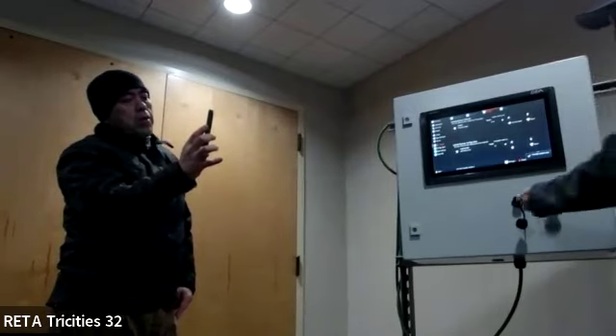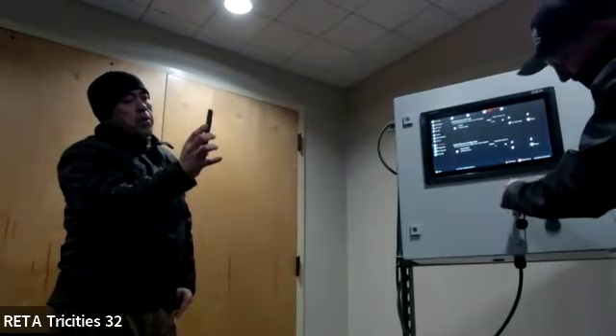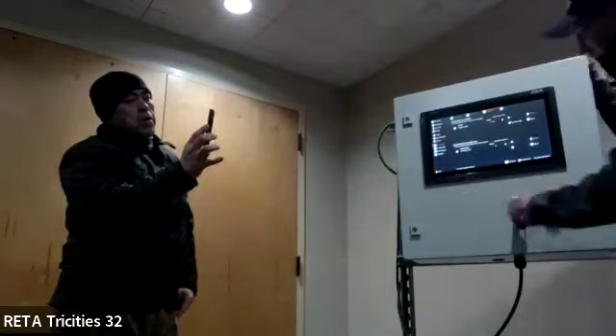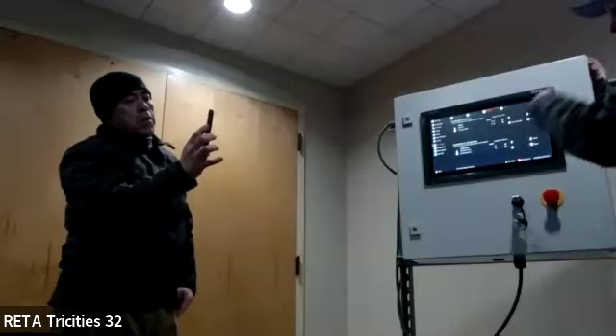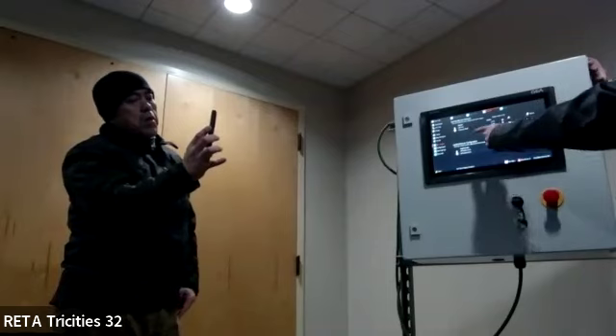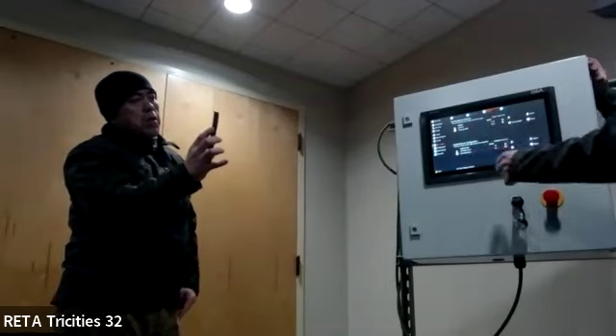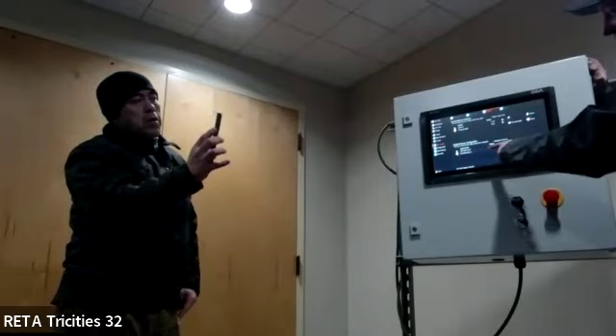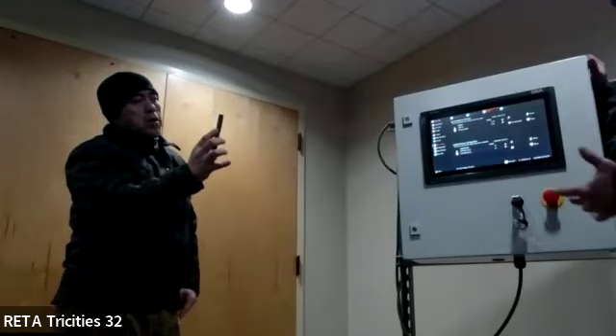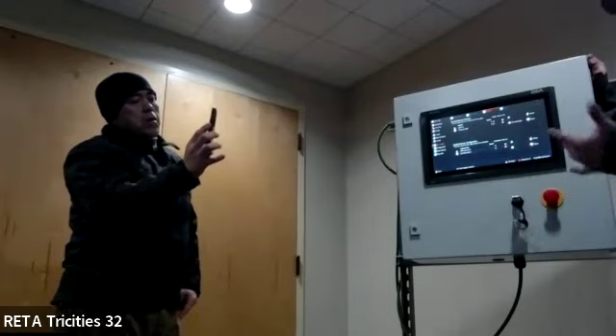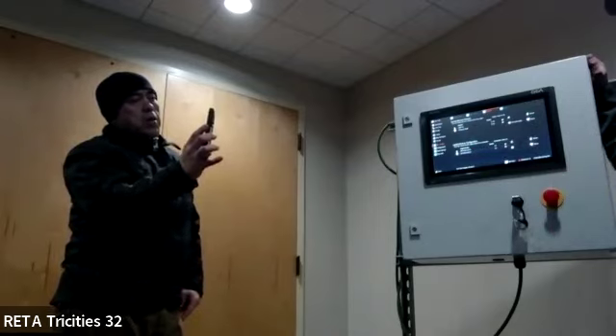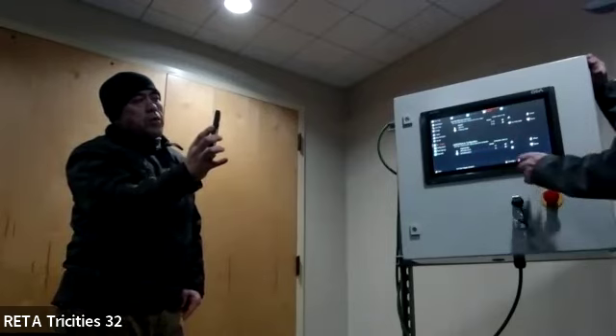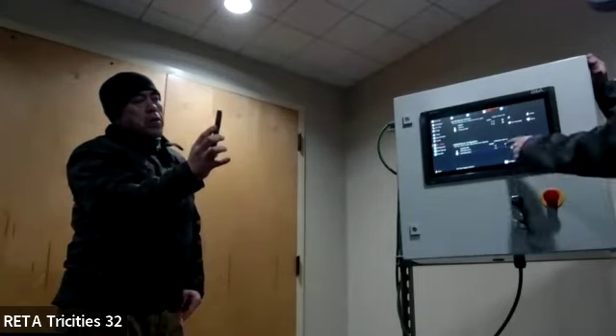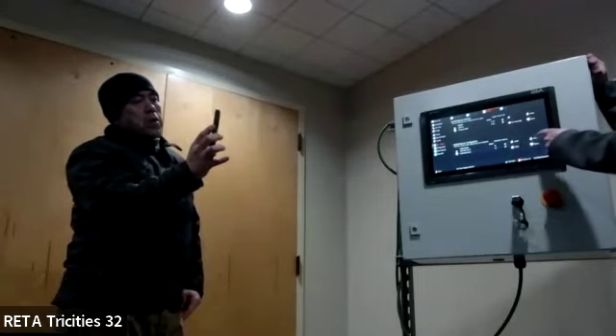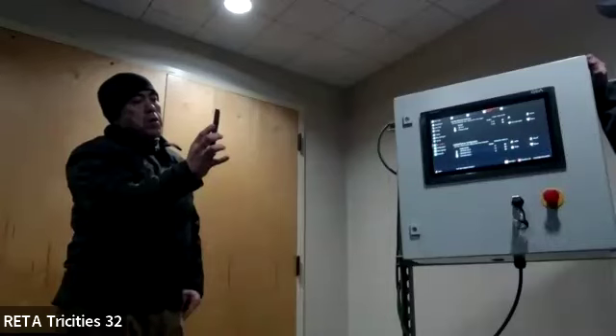So then you would take the USB drive and plug it in. It's going to show it. See, it shows USB drive version 1.743. That's what we just backed up on the panel. And then you have update configuration 1.1, because I have made a few changes here and there, so the configuration has changed since it came from GEA. You just click over here, check mark the box, and then you would back up to the USB drive. Same thing with the update.